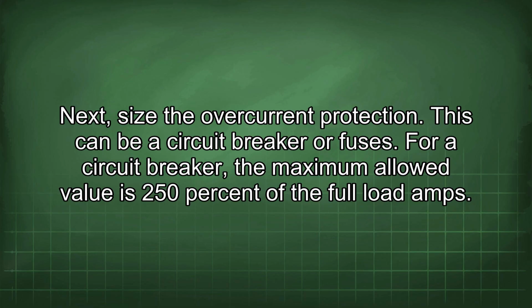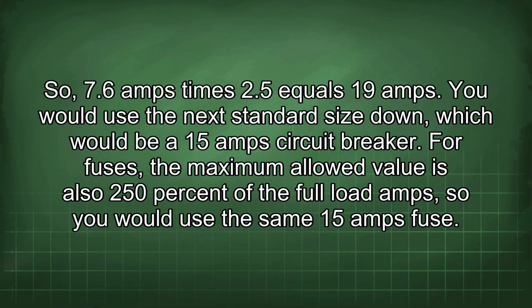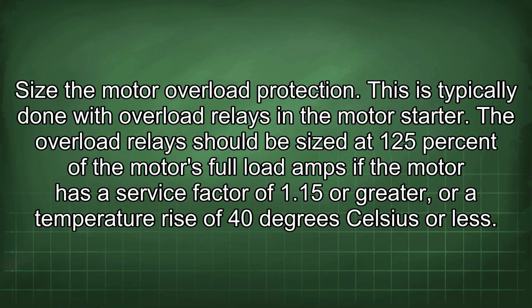Next, size the overcurrent protection. This can be a circuit breaker or fuses. For a circuit breaker, the maximum allowed value is 250% of the full load amps. So, 7.6 amps times 2.5 equals 19 amps. You would use the next standard size down, which would be a 15 amp circuit breaker. For fuses, the maximum allowed value is also 250% of the full load amps, so you would use the same 15 amp fuse.